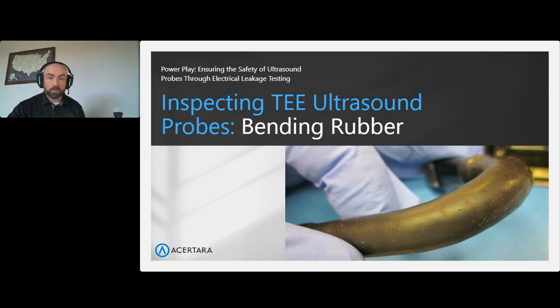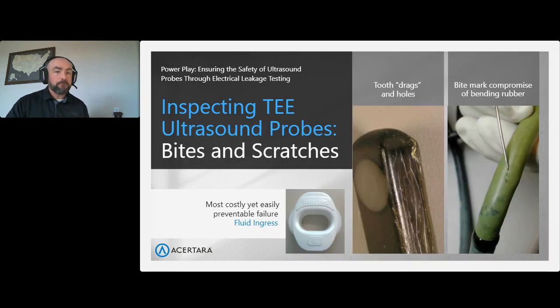So you can see the hole there. This is fairly obvious. I mentioned earlier tooth drags and holes. You can see on the center picture there a TEE probe tip. Those holes are all the tooth drags. Those are all areas where you should have concerns, right? It could cause failure of that probe when you test it on electric leakage, or it could be a spot for cross-contamination. And here you can see a bite mark on the articulation sleeve. I mentioned earlier, if you want to stop a lot of these things from happening: bite guards, bite guards, bite guards. That's how you save money, and it's how you make life easier for everybody involved in the process. I know that's not your choice, but if all of us harp on it, maybe someday the physicians will listen to us.